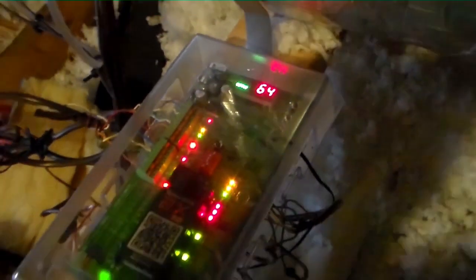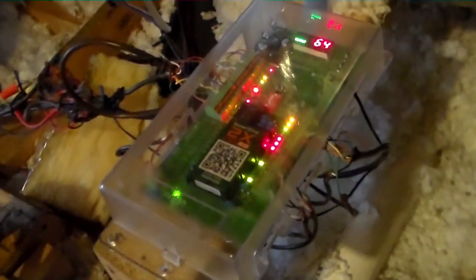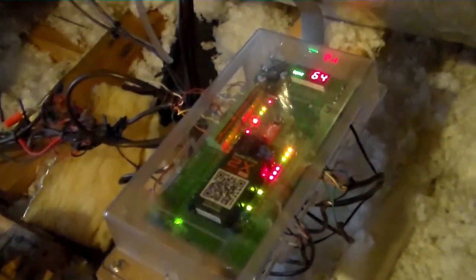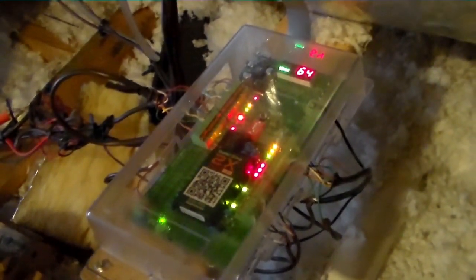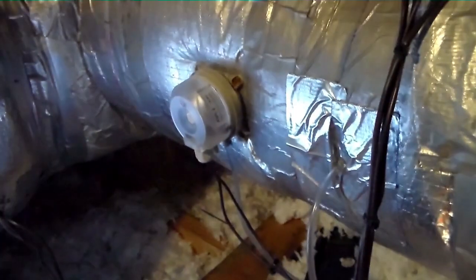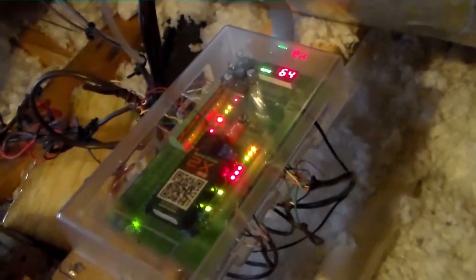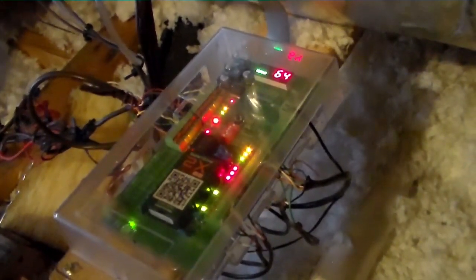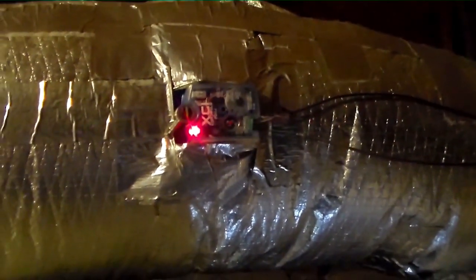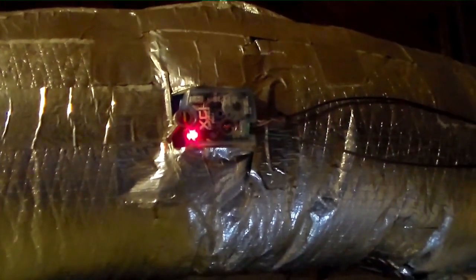We have 64 degrees coming out, about a 20-degree temperature split, still a little bit on the high side, but with the level of air noise from the extremities, that's where we're going to stay. We could probably bump it up to high and get a little bit closer to 400 CFM per ton, but for today and for the level of noise, and no one's going to buy a house when the registers squeal like pigs. So we're getting a decent amount of airflow, we'll say that.